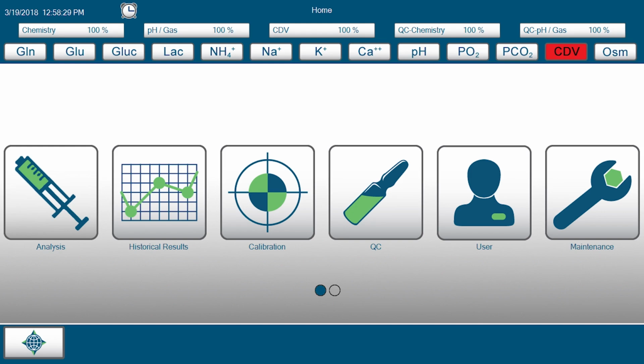When a parameter is not ready and is unavailable for sampling, the parameter icon will have a red background. A parameter may be unavailable for the following reasons. The parameter is uncalibrated. The reagent cartridges required by that parameter are empty, expired, or not installed. The MicroSensor Card for the parameter is expired, has reached the use life date, or is not installed. The wells required by the parameter for successful sampling are blocked.